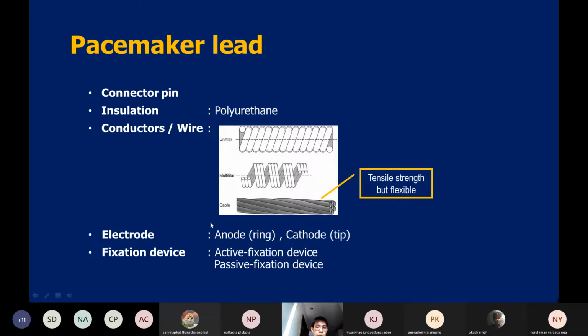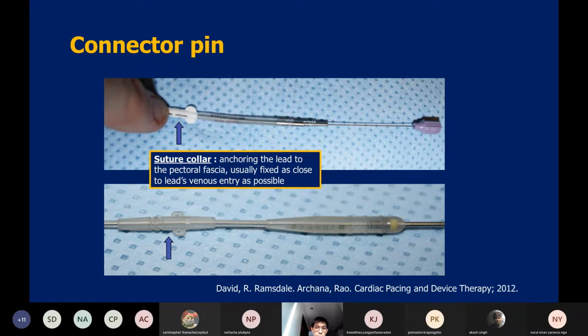We need electrodes, the anode and the cathode. The tip is the cathode and the ring is the anode. And the last thing we need is a way to fix the device to the myocardium of the patient. There are two types of fixation: the active fixation device and the passive fixation device. This is the connector pin, and this is the collar of the pacemaker, which is used to fix the leads.